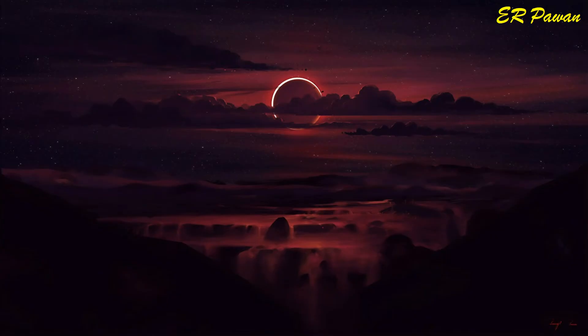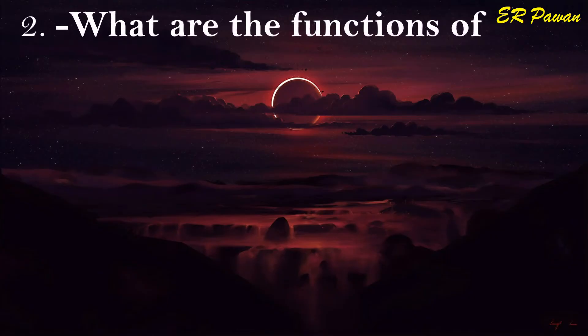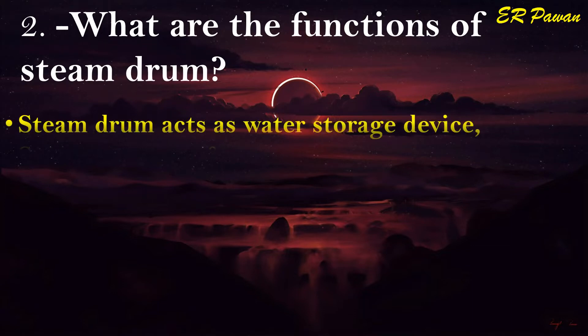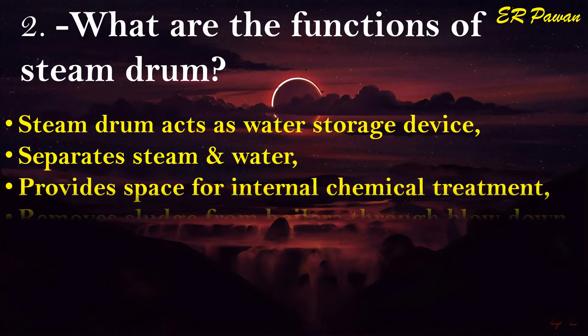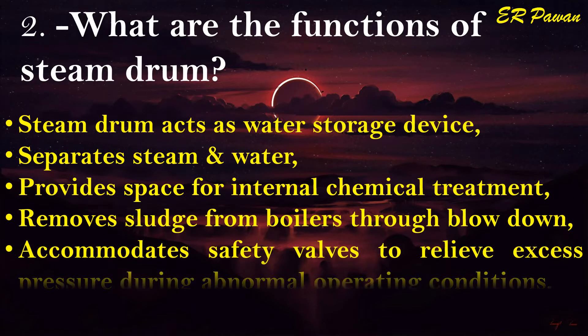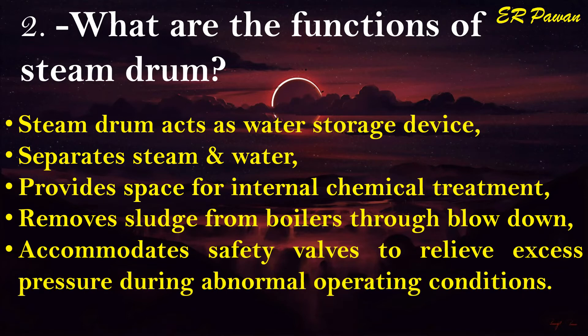Question 2: What are the functions of steam drum? Steam drum acts as a water storage device. It separates steam and water, provides space for internal chemical treatment, removes sludge from boilers through blowdown, and accommodates safety valves to relieve excess pressure during abnormal operating conditions.